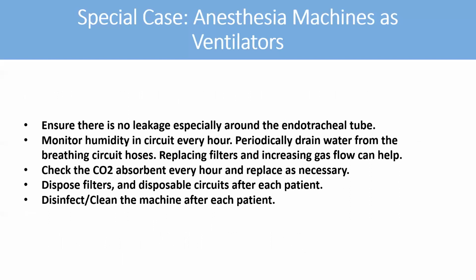This is another important thing. Make sure there is no leak in the circuit. Monitor the humidity in the circuit every hour, so you can check the water trap, all that. For the breathing hose, replacing the filter and increasing the gas flow can help. Check the CO2 absorbent every 2 hours or every hour, and you need to replace it. Dispose of the filter and the circuit after each patient. Clean the machine after each patient. Disinfect the machine, basically.